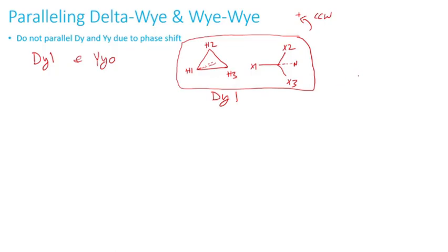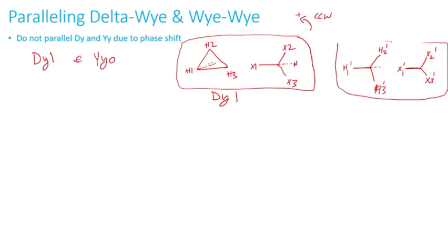Now I'm going to draw the yy0 transformer. I'll draw the high side windings calling them H1 prime, H2 prime, H3 prime to signify a separate transformer. Since there is no phase shift, these will be in parallel, so X1 prime, X2 prime, and X3 prime align directly. This is the second transformer: the high side is Y, the low side is Y, and there is no phase shift.